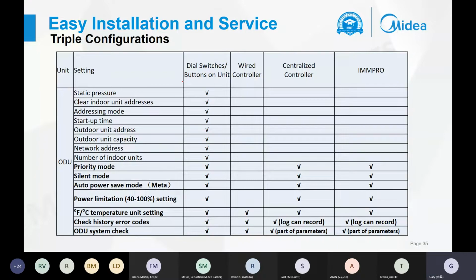For the dial switch buttons on the PCB of the outdoor unit, you can set all the functions, like the static pressure, the auto mode, or the start-up time, and the outdoor unit can track all the functions you select by the dial switch of the outdoor unit's PCB. And with the wire controller, you can set only these 3 parts: the F or C temperature unit setting, or track the history error code. The wire controller will show the history error codes.